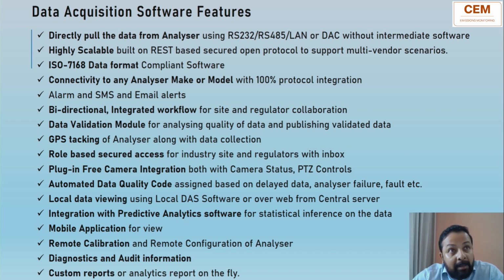The data at the central server can be seen anywhere by the respective software and authority provided. This can be integrated with predictive analytics software, and you can view it on mobile. Remote calibration and remote configuration of the analyzer are possible with this data acquisition and handling system. Diagnostics and audits can be carried out, and these records are inbuilt in the system.